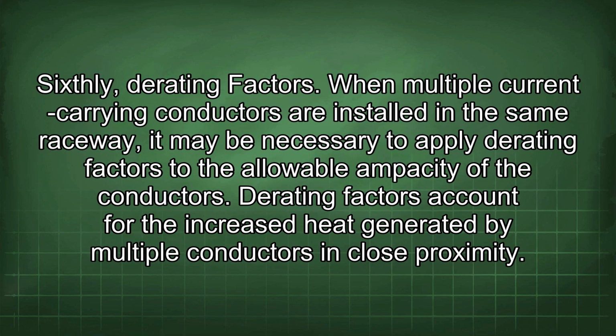shock. Sixthly, derating factors. When multiple current-carrying conductors are installed in the same raceway, it may be necessary to apply derating factors to the allowable ampacity of the conductors.